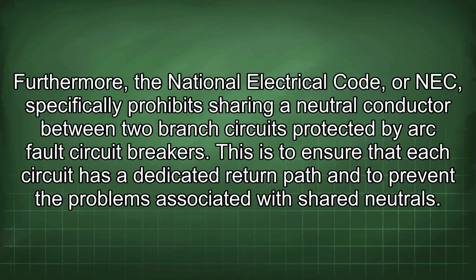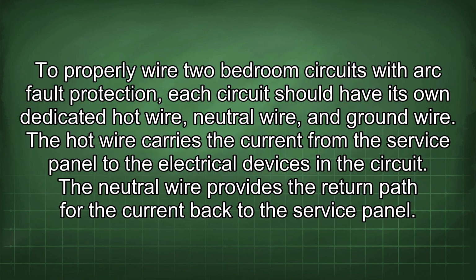Furthermore, the National Electrical Code, or NEC, specifically prohibits sharing a neutral conductor between 2 branch circuits protected by arc fault circuit breakers. This is to ensure that each circuit has a dedicated return path and to prevent the problems associated with shared neutrals. To properly wire 2 bedroom circuits with arc fault protection, each circuit should have its own dedicated hot wire, neutral wire, and ground wire.